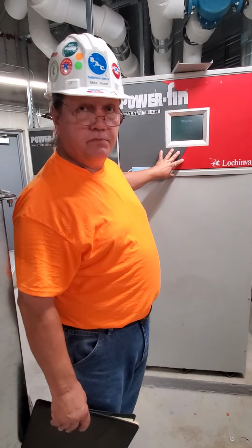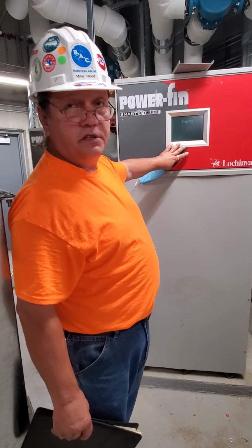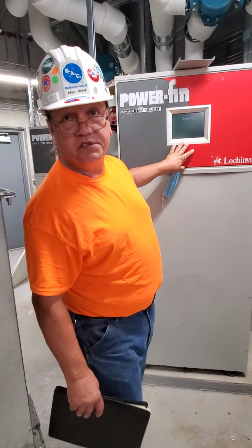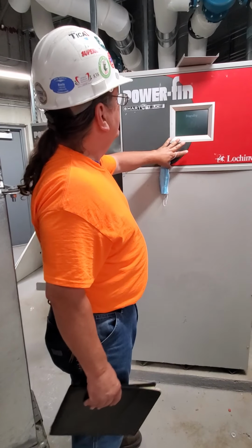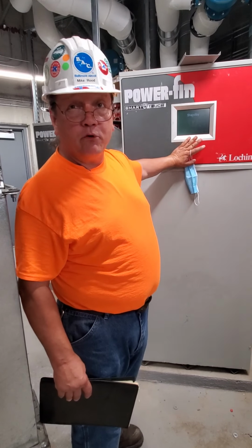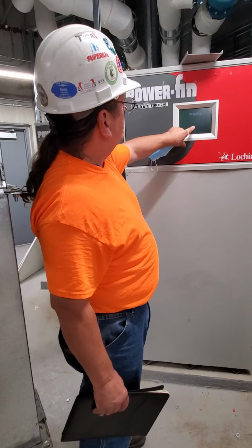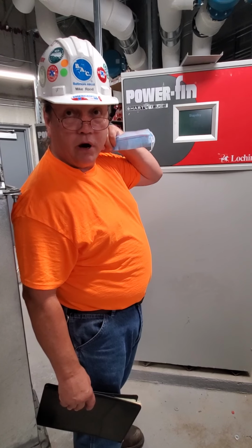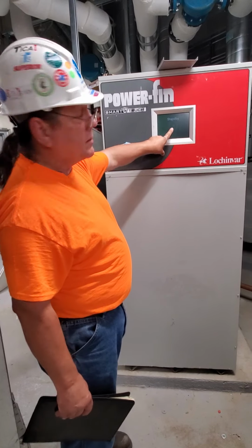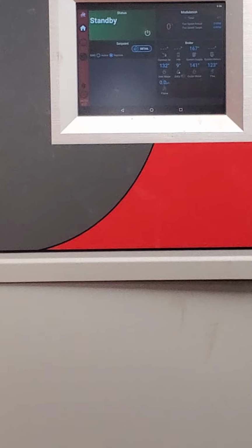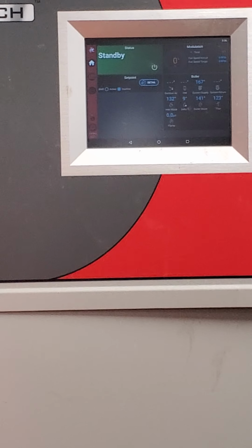Basic access of this boiler for controls. This is the normal screen you'll see when you walk up to it. This is a standby screen. It's also in screensaver mode. Okay, so it'll tell you how much it's firing, if it's running, or what percentage of firing it's running at. To get into the screen, all you have to do is touch it, and you'll see the normal screen pop up.